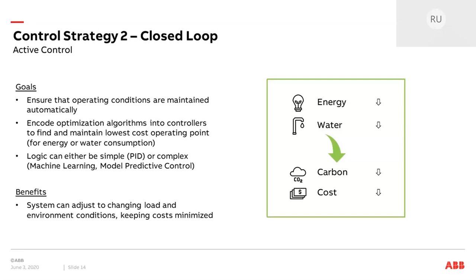Generally, using closed loop control for cooling applications, you can actively control to lower energy or water usage. It could be based on a single unit, like a single CRAC or CRAH, or used across a number of units in an area. So if you're coordinating the control of a number of cooling elements within a single data hall, for example, or it might be across the whole data center.